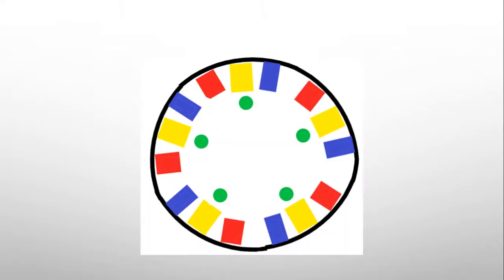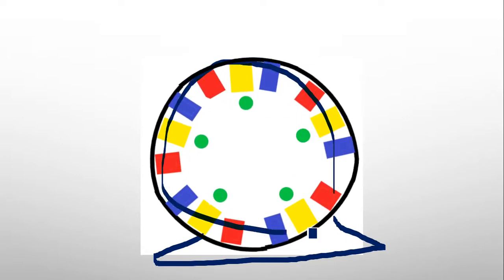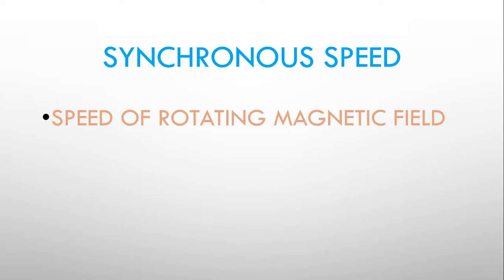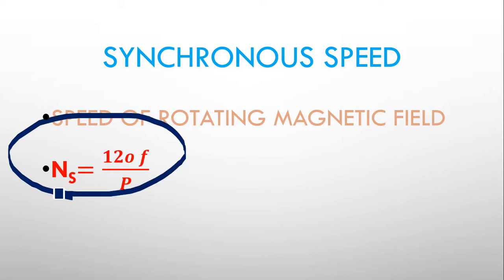Similarly, in a three-phase induction motor there is a revolving magnetic field called the synchronous speed. Its equation is N_s = 120f / P. As the number of poles increases, speed decreases. As frequency increases, speed increases, but normally frequency is fixed at 50 Hz or 60 Hz.